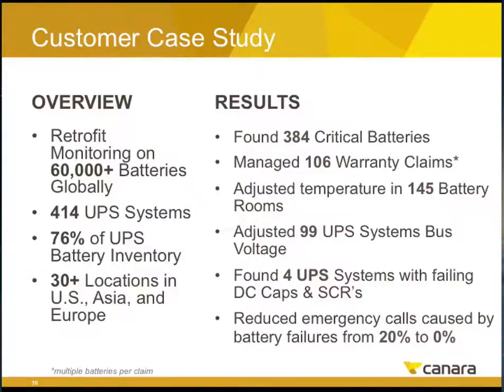The next few points show some of the other things we do and really dramatize how we work operationally with our customers. On a daily and weekly basis, we'll notice things about the batteries: are they at the right temperature, are the bus voltages right, is something going on with the UPS system? Importantly, our technology monitors AC ripple current, which can be very damaging to batteries and is also indicative of potential failures on the UPS system. So oftentimes, even if the UPS system isn't technically in alarm, we'll notice things starting to come out of spec, and we'll let the customer know.